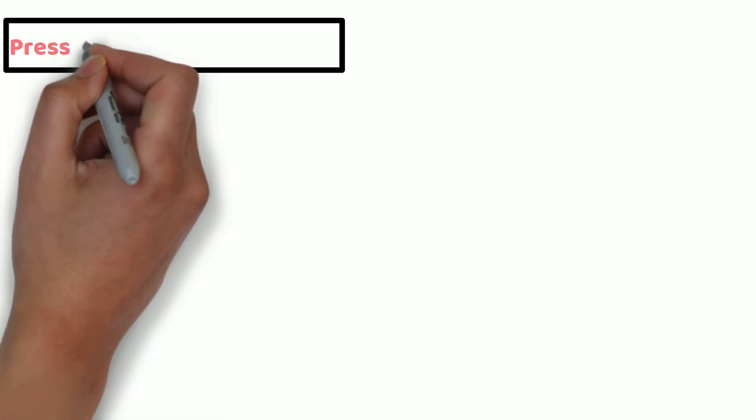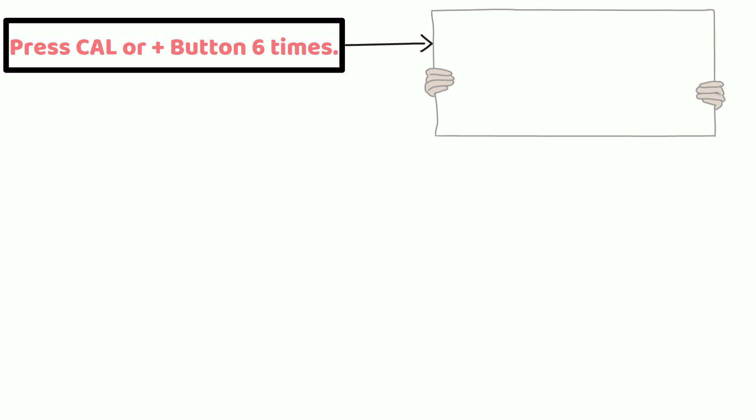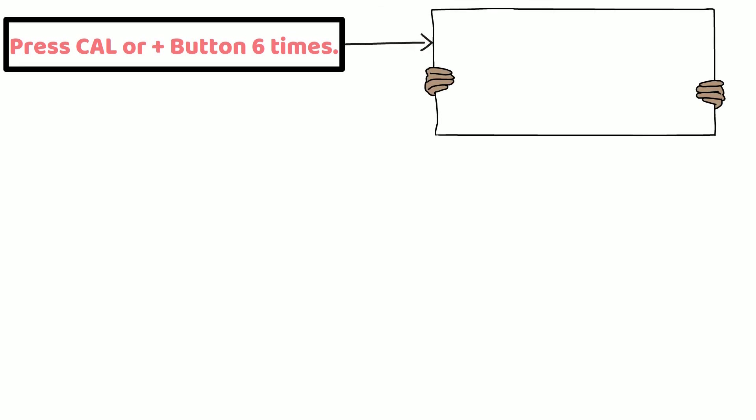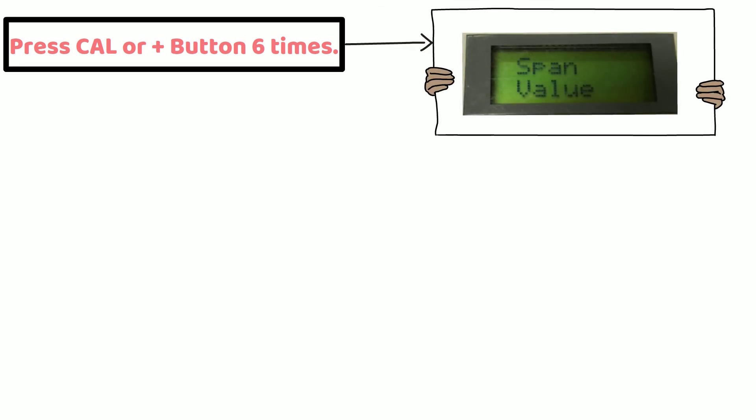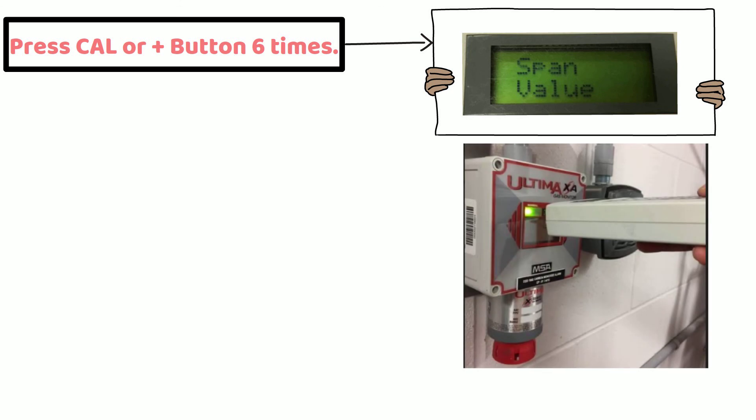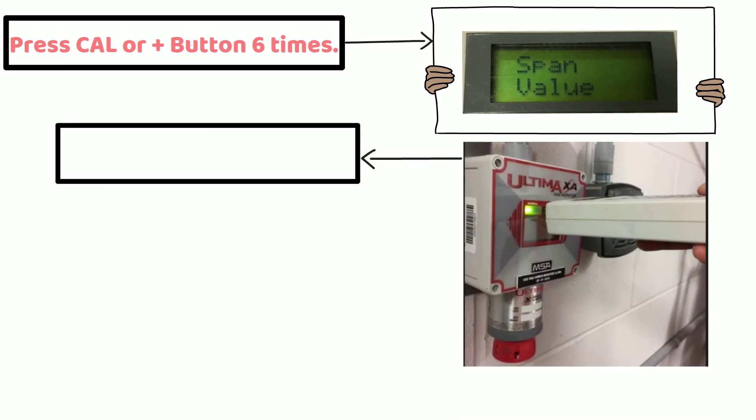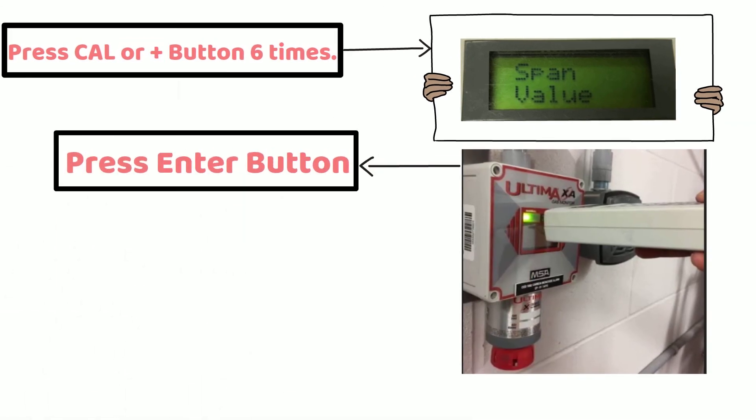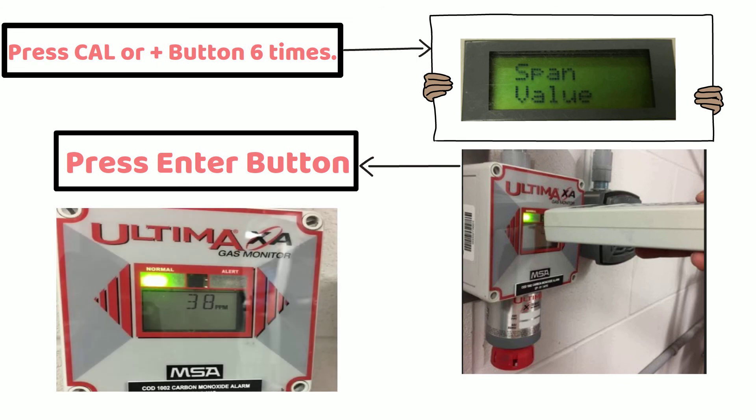For example, if I want to check span value, I will press cal or plus button six times. When you see span on controller display, point controller towards transmitter and press enter button. Span value will appear on transmitter display for three seconds. Note down span value since you need to use same concentration gas to calibrate the transmitter.